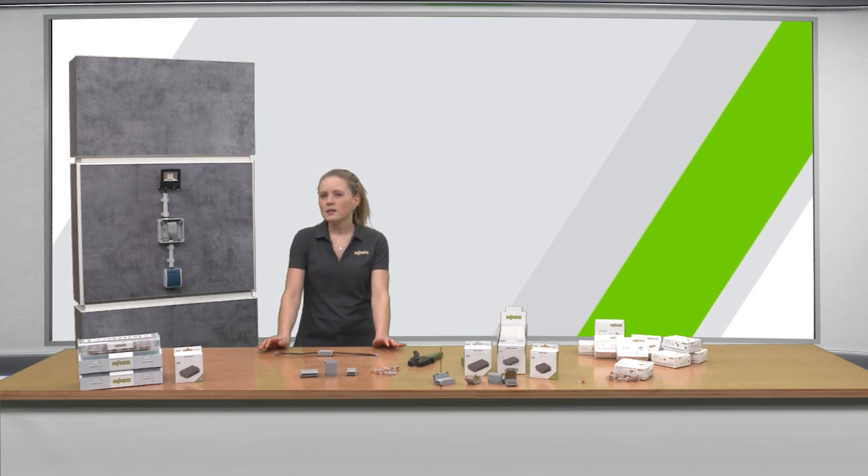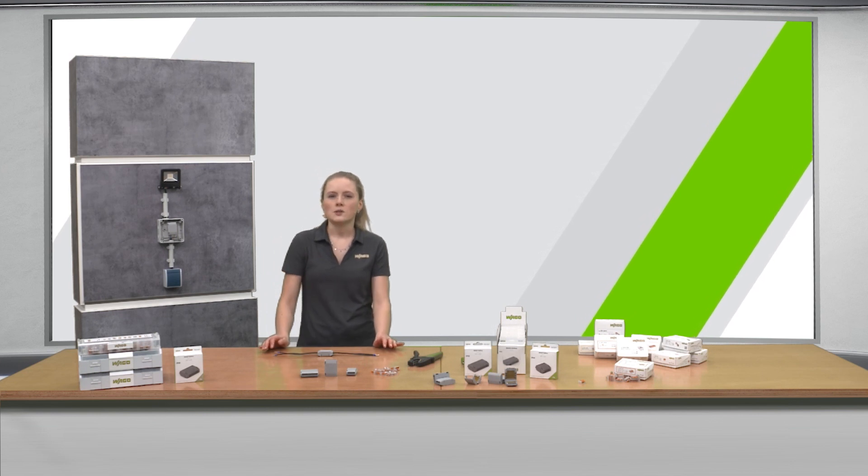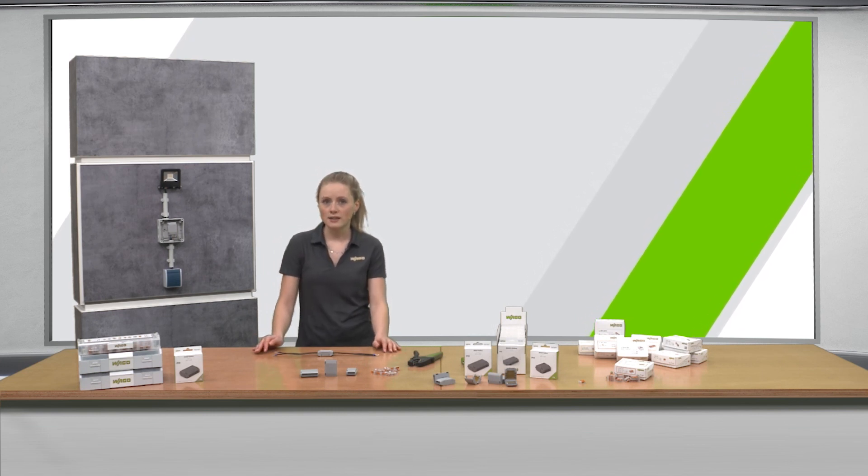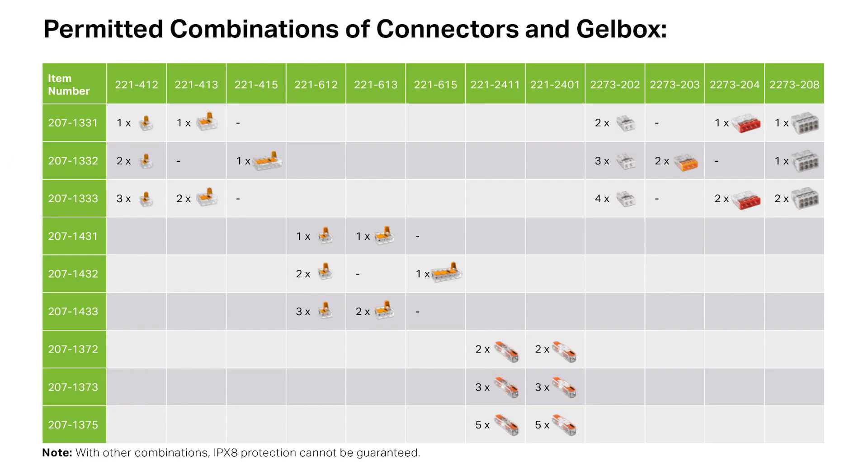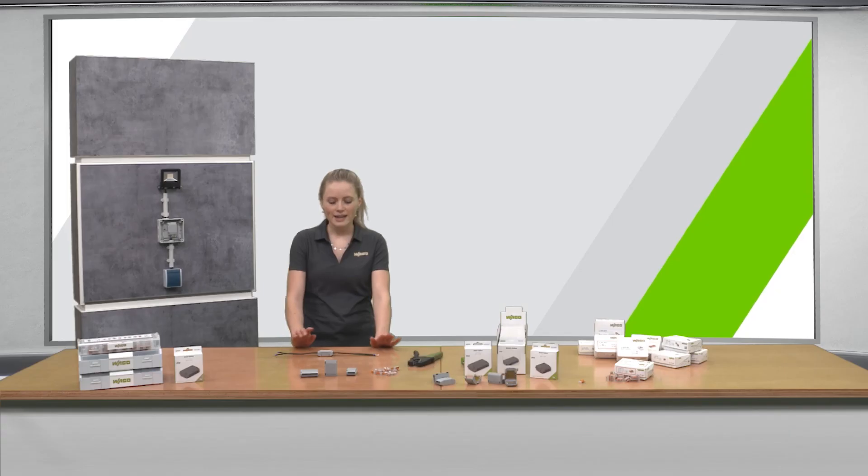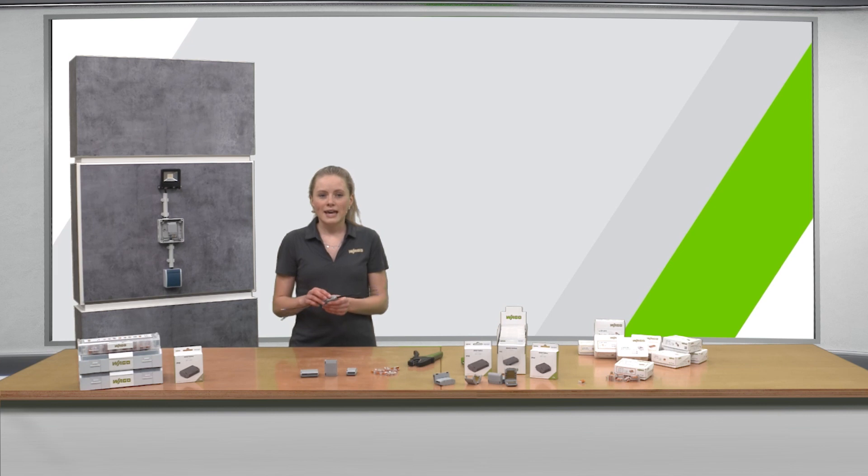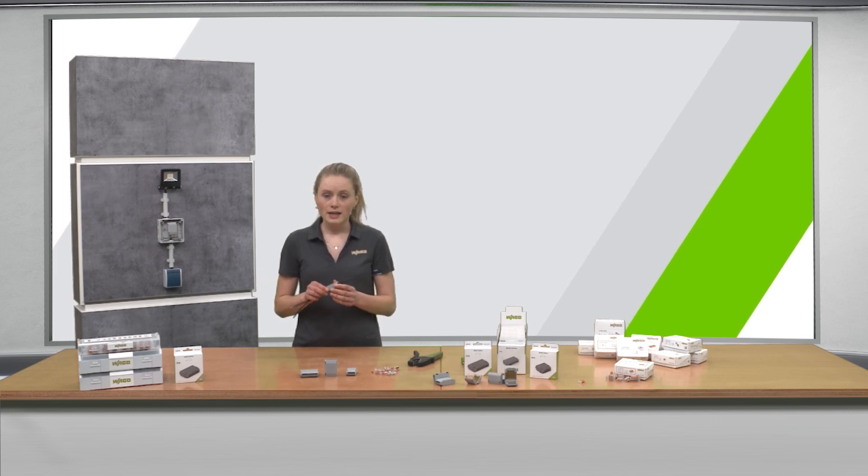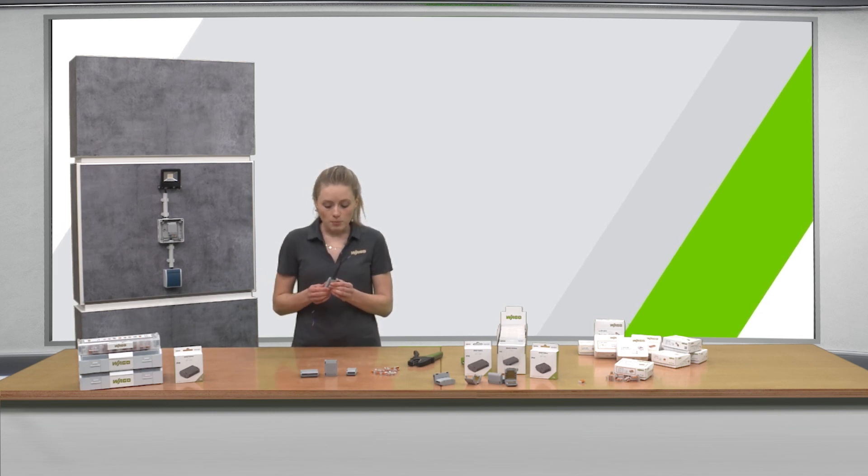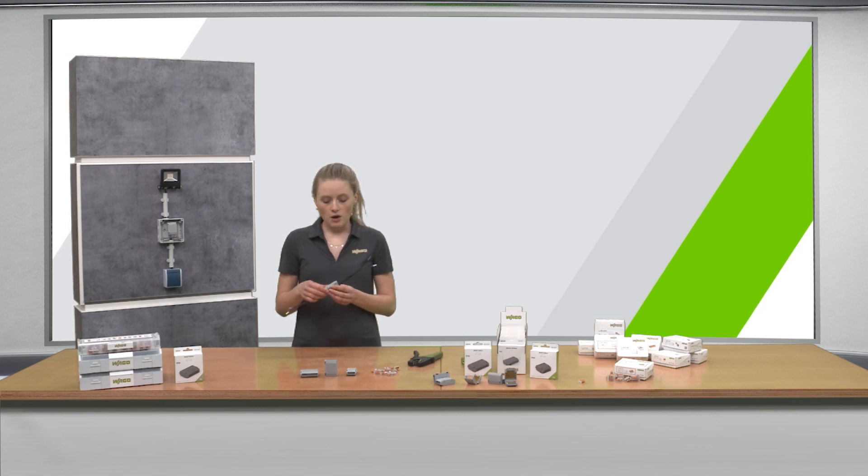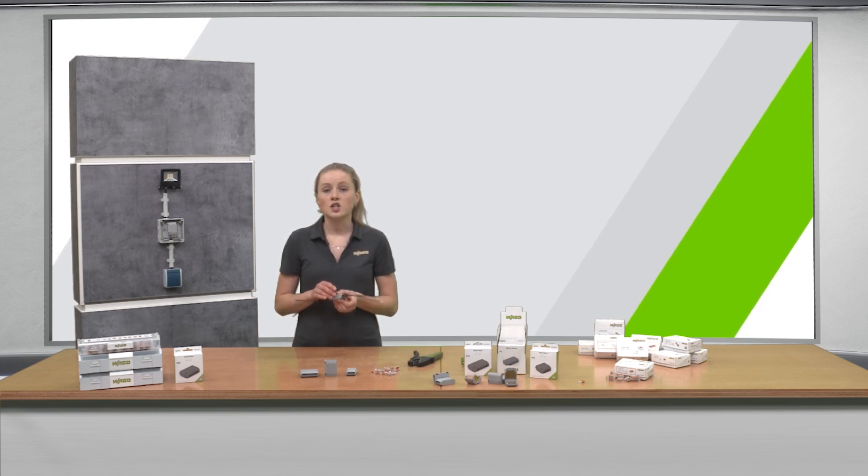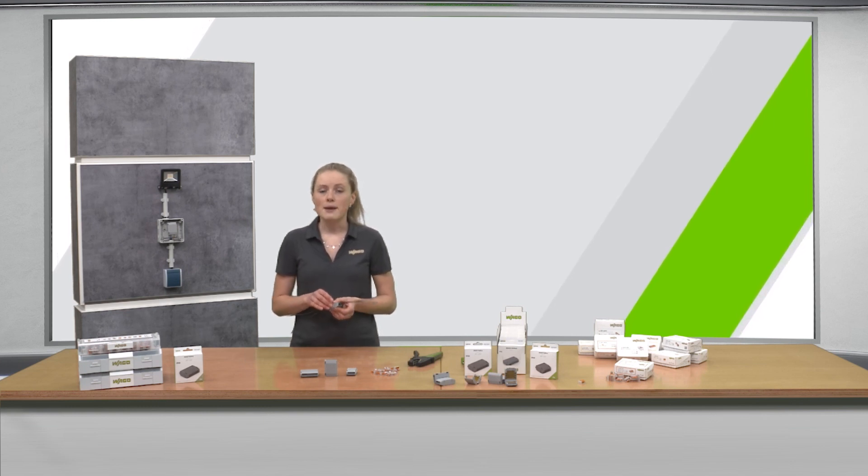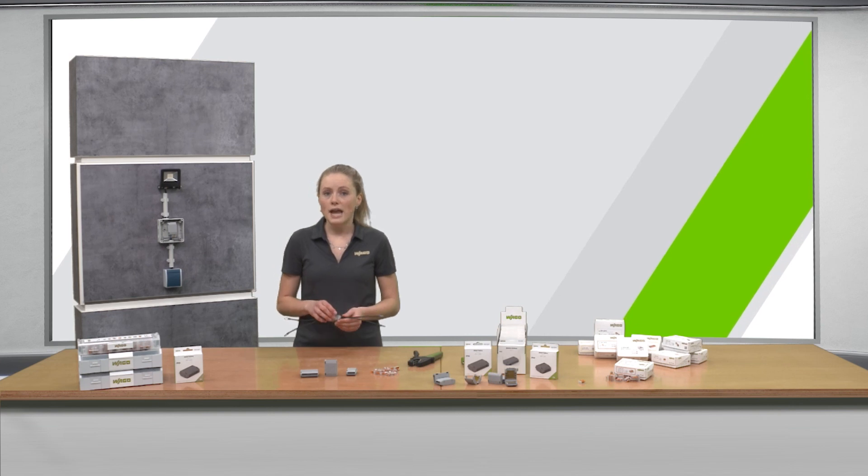When using the gel box it is important to consider the assignment table to guarantee the optimal gel displacement and also the high IPX8 protection. This means that I cannot put only one inline connector in the gel box for two connectors because the displacement of the gel is then too low and moisture will enter.